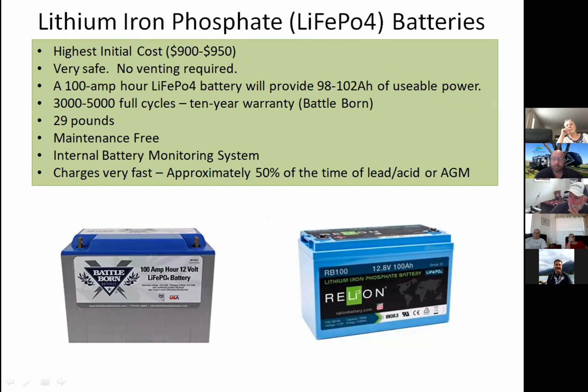The Cadillac of batteries is a lithium iron phosphate battery. They have a pretty high cost. When I made these charts, they were around $900 to $950 each. I've seen some brands at Costco that can be on sale for down in the $675 and up range for some of the batteries that are offered there. These things are very safe. There is no venting required. Now, a lot of people think lithium batteries have a bad history and they've exploded, caught on fire. That is true, but those are not lithium iron phosphate batteries. Those are strictly lithium ion batteries.